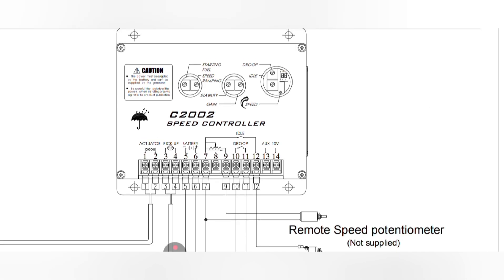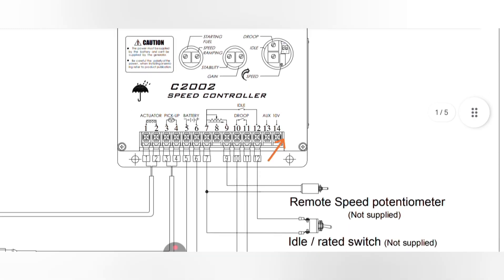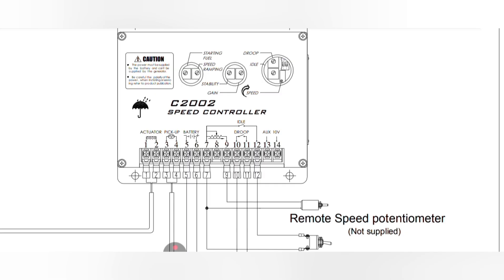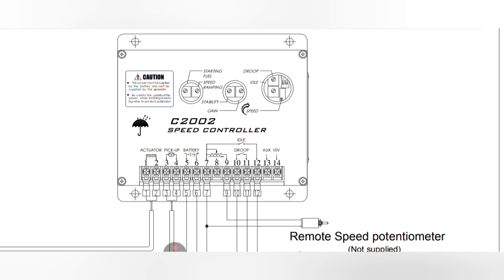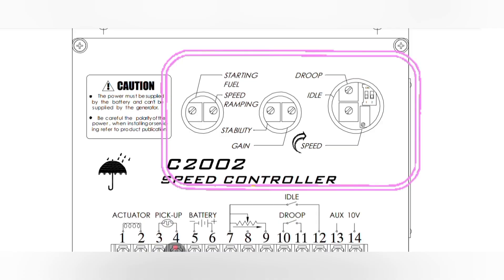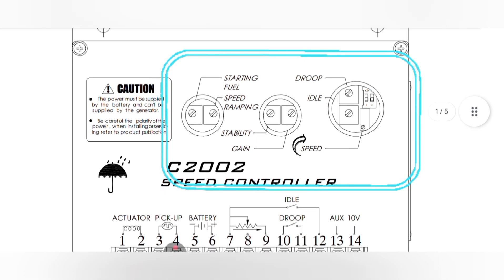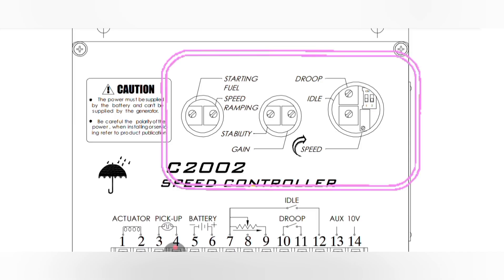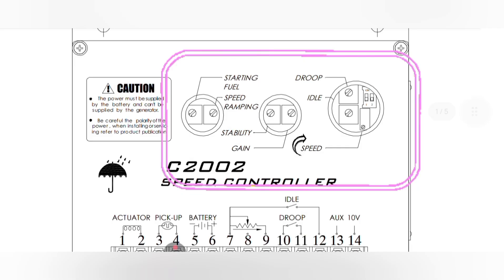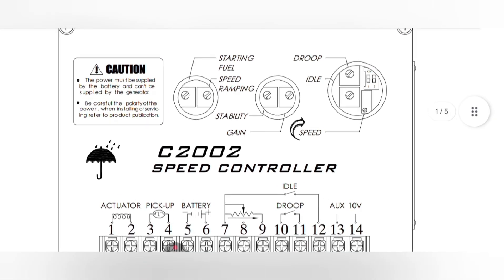Pins thirteen and fourteen are for the auxiliary connection — an extra connection that can be used for other purposes, providing a 10-volt DC output supply with an on/off switch. Moving to the adjustment setup: here we have starting fuel adjustment, speed ramping adjustment to control speed fluctuation, engine stability and governor stability, voltage gain, droop setting, idle speed, and direct engine speed increase/decrease — all adjustable via their respective potentiometers.